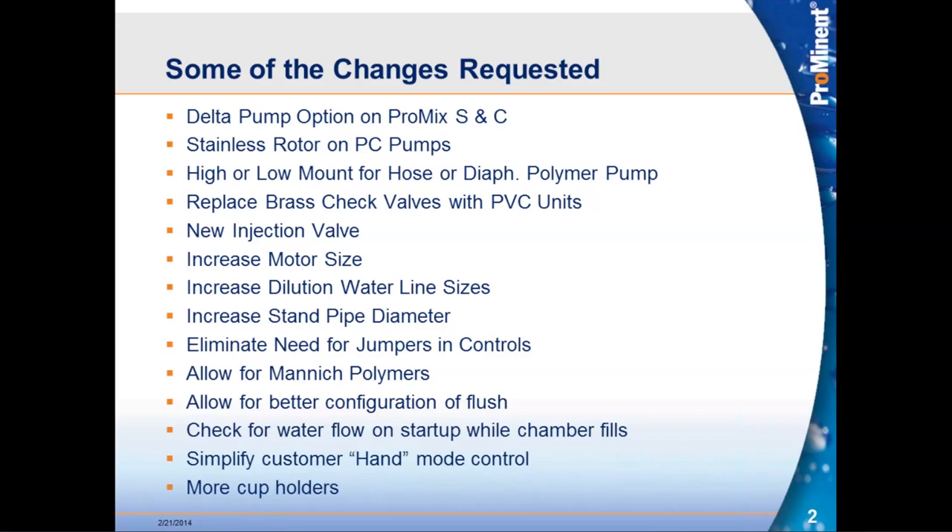Eliminating jumpers and other internal modifications inside the controller that operators needed to make when systems were first installed, minimizing the need to open the control panel just to get a system up and running. We also wanted allowances for Mannich polymers, better flushing configurations, checking water flow on the chamber during initial fill to prevent seal failures, and simplifying hand controls so operators can make changes via switches rather than menus.